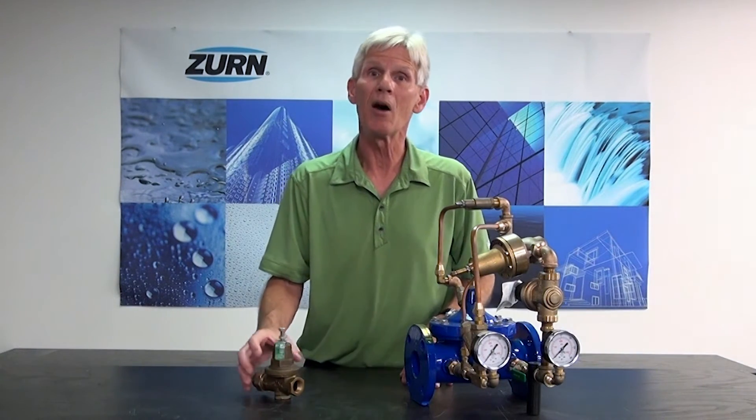With respect to accuracy and how well they deliver fluid — in this case, the pressure reducing valve — we're going to want that pressure to be delivered virtually constantly. When we compare to a direct acting pressure reducing valve, they exhibit a characteristic called fall-off. Fall-off is basically the change in outgoing pressure when going from a static condition to a flowing condition. The more water that a direct acting pressure reducing valve flows, the lower the downstream pressure will become. In many applications that may not be a problem, but in industry or even some housing situations, we demand constant pressure regardless of flow rate. The automatic control valve of the pressure reducing variety can deliver constant pressure regardless of flow rate or changes in inlet pressure — and the direct acting PRV just can't do that.